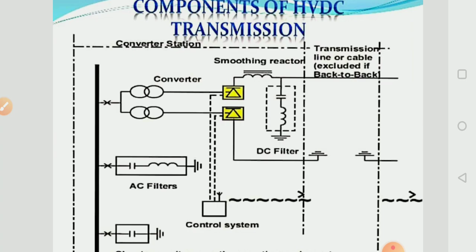Now, what are the components in the transmission line? Here we use the converter. We use the converter for AC to DC conversion and DC to AC conversion, and it includes the transformer and bridges. The next is the smoothing reactor, in which an inductor is connected in series with the pole. It is used to avoid commutation failure occurring in the inverter, and it also reduces the harmonics. Another advantage of the smoothing reactor is that it avoids discontinuity of current for the load. That's why we use smoothing reactors in these HVDC substations.